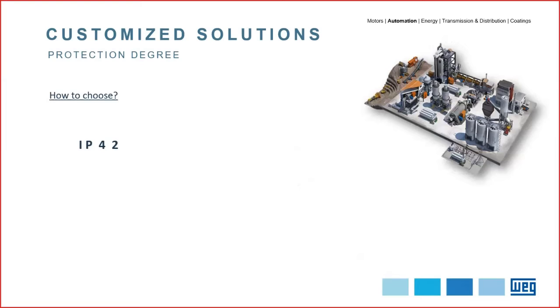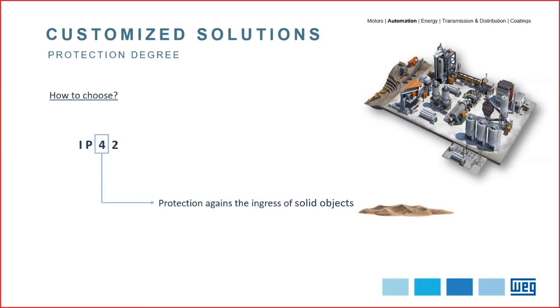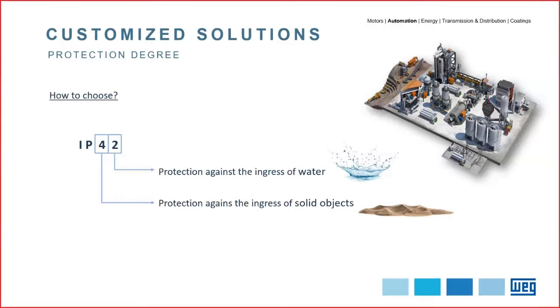And how to choose the IP code? The first characteristic numeral indicates the degree of protection against the ingress of solid objects and against the access to hazardous parts. The second characteristic numeral indicates the degree of protection against the ingress of water with harmful effects. So the higher the number, the higher the protection.